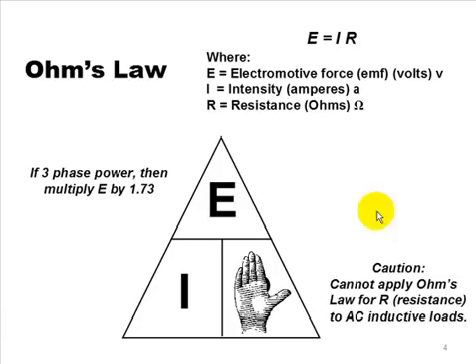When you put your Ohm meter across the windings of that motor, it's going to come out nowhere near what Ohm's Law is going to come out to because your Ohm meter has a battery in it and it's sending voltage through that coil and that voltage is generating a magnetic field which is opposing the flow of that battery current through that very coil you're testing. So it gets very funky to say the least. But just remember, don't apply this Ohm's Law to AC inductive loads.